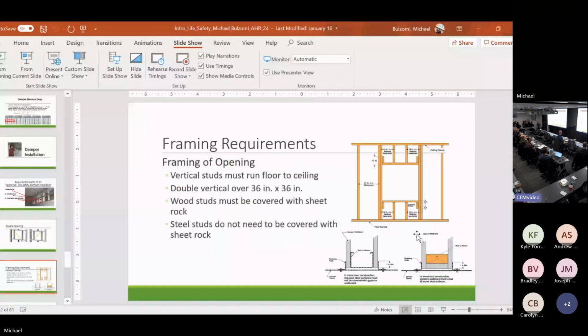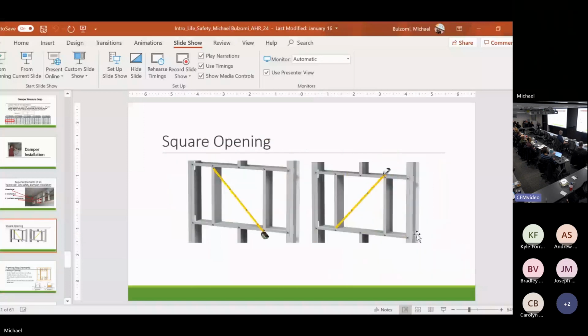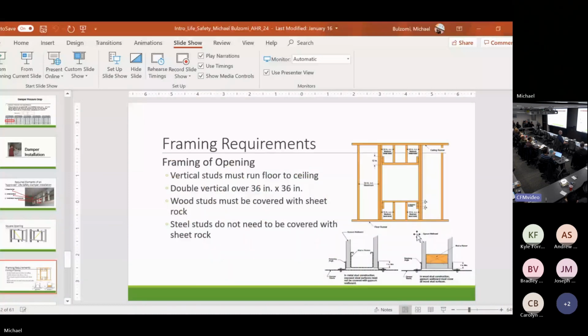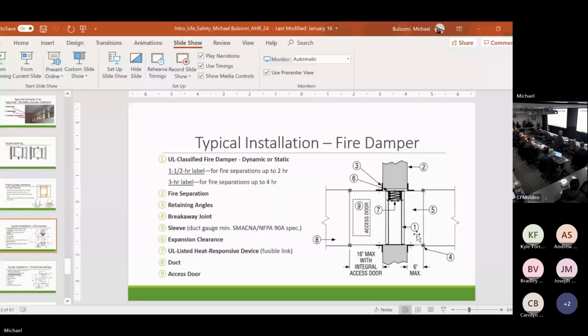But certain things we always want to tell them to make sure, like we're not responsible for the building of the partition, but my contractor goes up there, we tell them make sure the openings are square, right? Dampers must be square, plumb, straight. Want to make sure that they're framed appropriately. And if there's a problem with the framing, and the contractor says, hey, studs are supposed to run floor to ceiling, 12-foot, my GC made a mistake, he ordered 10-foot. He wants to splice them. Is that okay? So I don't know, ask the authority having jurisdiction. If he approves that barrier construction, then you can install my damper. I don't approve barrier construction.